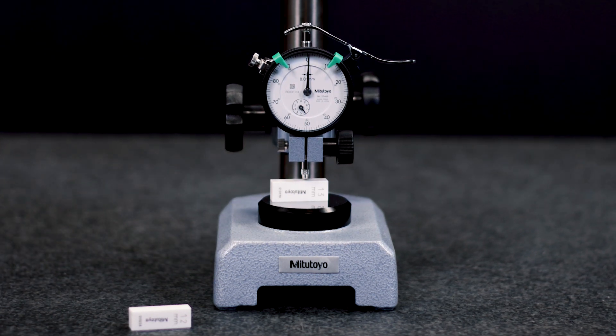The unskilled operator forgets to pay attention to the small pointer that indicates the full millimeter and just reads the long one, which shows the feature inside tolerance, referred to the tolerance marks.